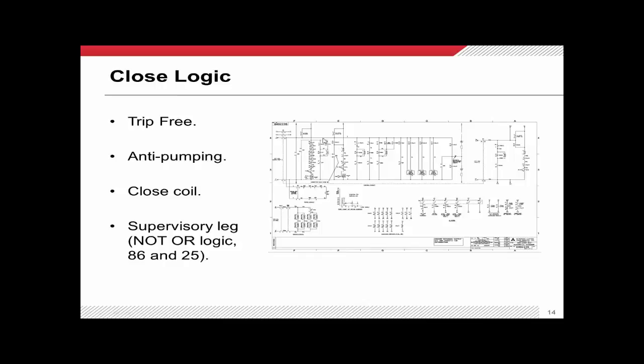The close coil is located here — that squiggly line — and all of these features above it, which are NOT-or logic, are the things that supervise closing. These are all the features that, if not in the correct state, mean we do not want to close this circuit breaker. If you take this lead out to your substation control building, a couple more things will be added in the next class — specifically ANSI numbers 86 and 25 — to prevent closing if they're not in the proper state.